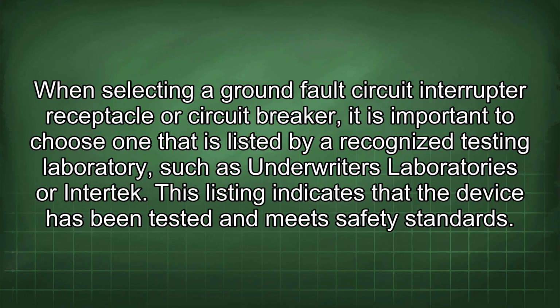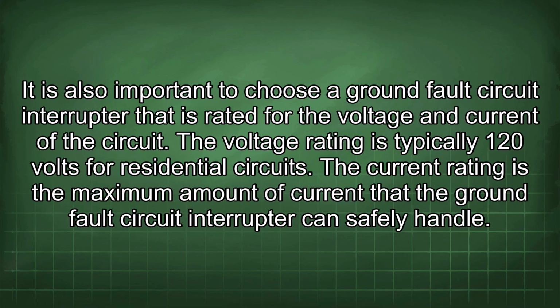When selecting a ground fault circuit interrupter receptacle or circuit breaker, it is important to choose one that is listed by a recognized testing laboratory such as Underwriters Laboratories or Intertek. This listing indicates that the device has been tested and meets safety standards. It is also important to choose a ground fault circuit interrupter that is rated for the voltage and current of the circuit. The voltage rating is typically 120 volts for residential circuits. The current rating is the maximum amount of current that the ground fault circuit interrupter can safely handle.